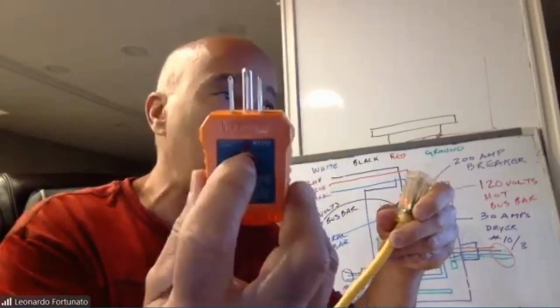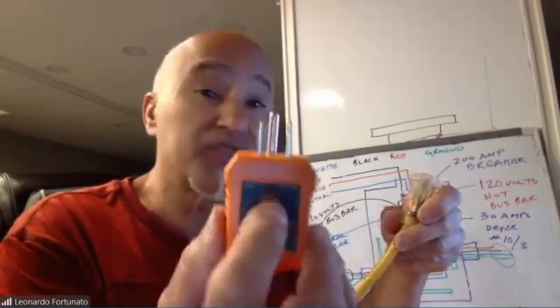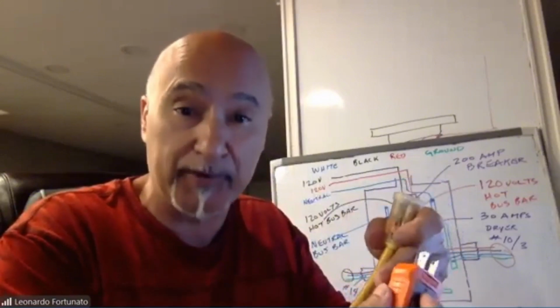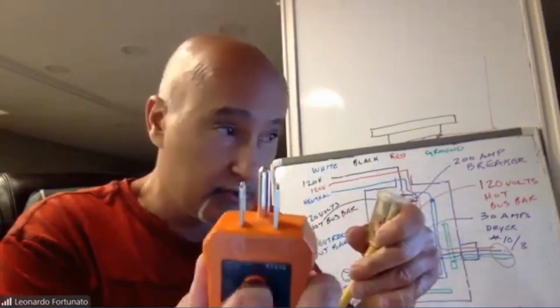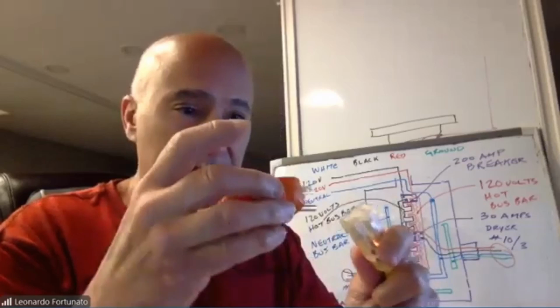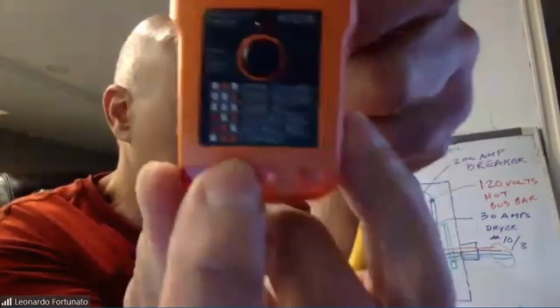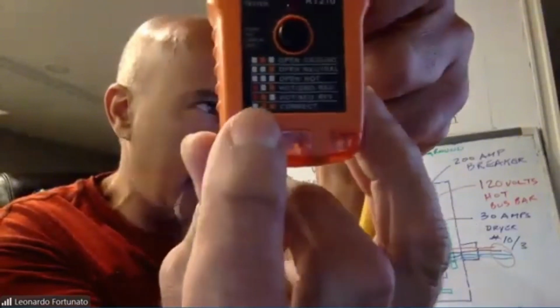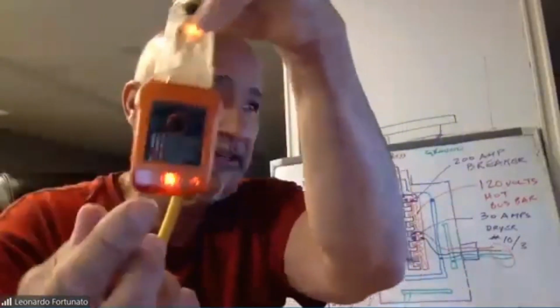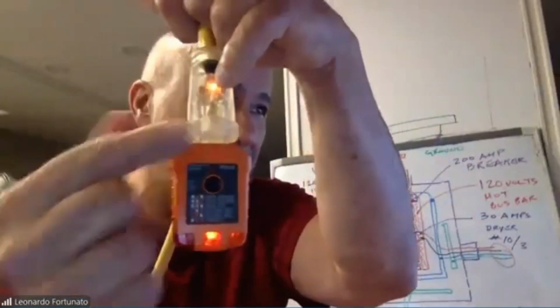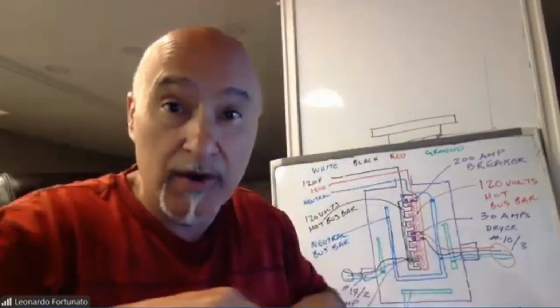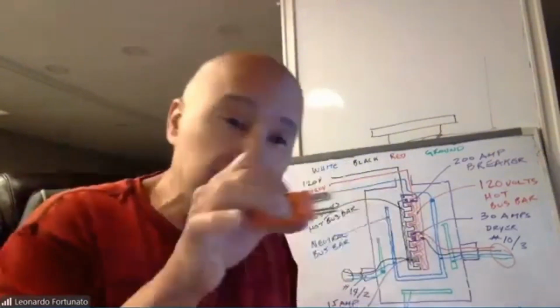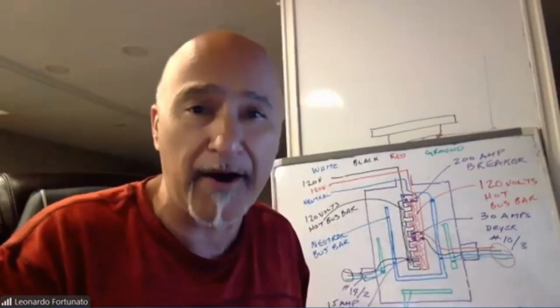This allows me, by pushing this button in, to test that function on those receptacles as well. If I plug this in, look at the bottom, it'll show you if these two lights on this side go on, it's correct. Since I wired this and know it's correct, you'll see those two lights went on, so my connections were done properly. So very quickly in a home, I can plug this in my receptacles and see if they were wired properly.